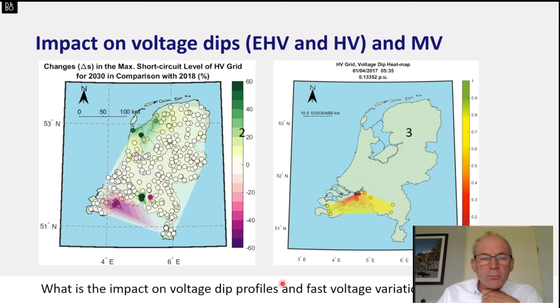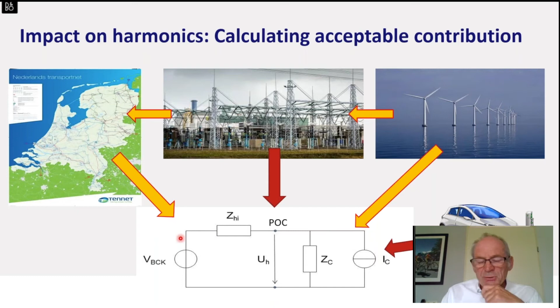Another research that we are doing is the impact on harmonics, because we have a lot of new renewables connected to the network, new technologies, both for renewable energy production but also for electrical vehicles. It's very important to look at the harmonic currents that they are injecting into the network, and what the influence is on the harmonic voltages at the point of connection. So what is injected into the network from these renewables or electric vehicles? What is the harmonic background that was already there, and what is the impedance of the network? Because all these factors are important for calculating the harmonic voltage at the point of connection.